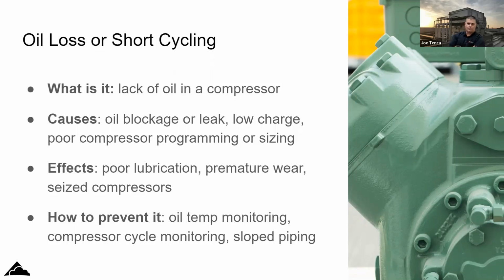And it always seems to happen when you're not there. It never happens when you're on site. There's a compressor trip in front of you and you go, oh, look, there's no oil in the sight glass. Or no, look, the sight glass is full, but it pumped the oil out real quick and refilled instantly. So it's definitely a tricky thing to find. And it's very complex. All the oil systems are different. You've got some that are high pressure, low pressure, some that use an OCD off the top of the reservoir, some that use the little oil valves.